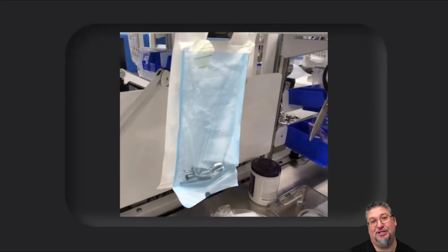Now there's a burnt indicator as well, which means there were some other issues going on with this heat sealer, but the damage you saw previously was because that heat sealer bar was not being rotated. So if you have that bar heat sealer, I can't remember if it's monthly, I want to say it's every month you're supposed to be rotating it, but just make sure you're looking at it and making sure that your seals are in good shape. There are tests as well. So there are peel pouch tests, and you can see here the ink is starting to leak through the pouch. A perfect sign that your heat sealer is probably not working the way it's supposed to, because it should be, again, an airtight seal.